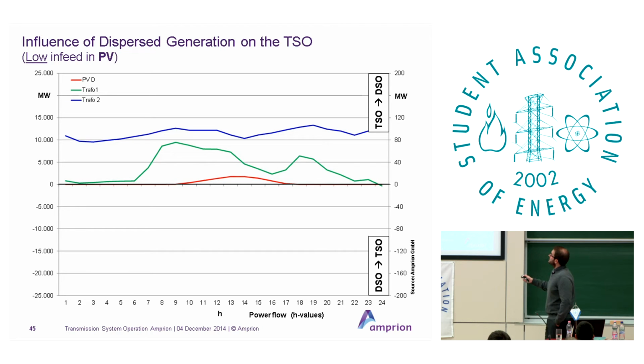Here's an example of a day with low PV infeed, just photovoltaic, around 2,000 megawatts peak. In green and blue are two examples of transformers connecting the DSO and TSO grids—connection points showing load flow between them. Above this line, we have flow from TSO to DSO grid, which is the usual direction, as it has been since transmission and distribution systems existed.